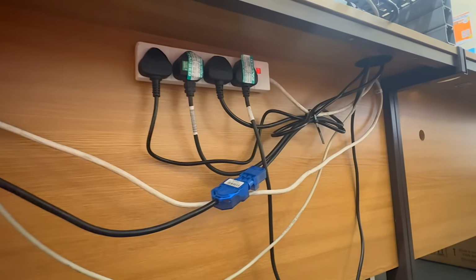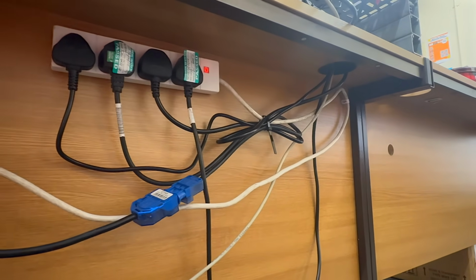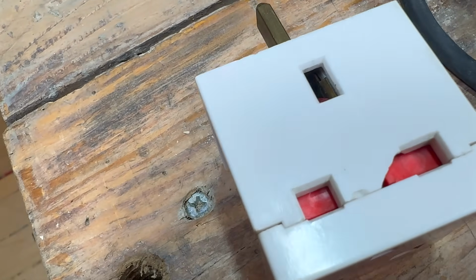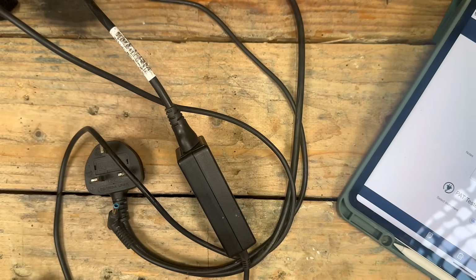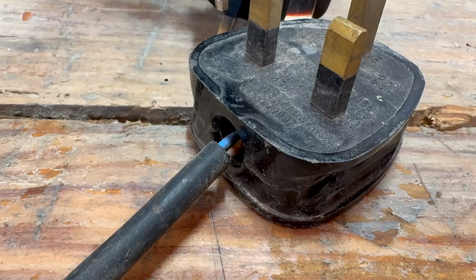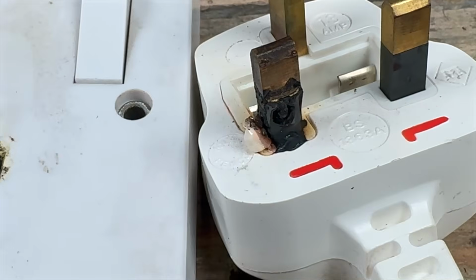They check whether the equipment has a legible label if the organisation uses them. Having no label doesn't mean it's unsafe. We covered that earlier in a video, but if the organisation uses labels, then they should be intact. Then comes the visual inspection. The plug, the flex, the casing, the strain relief, the controls, the general condition. Crushed cables, exposed copper, burn marks, loose parts, cracks, missing screws, anything that suggests damage or unsuitability for the environment.